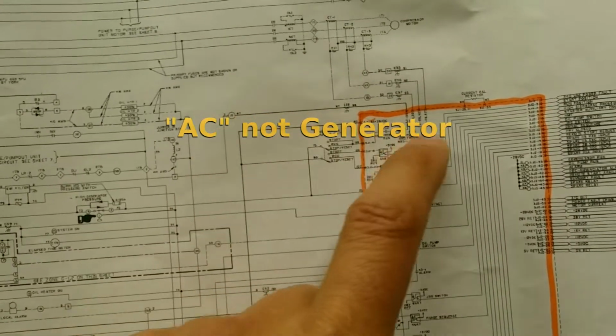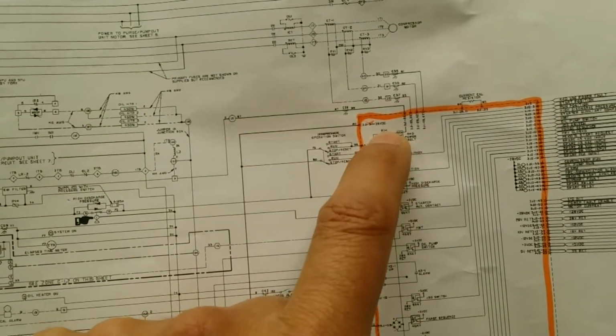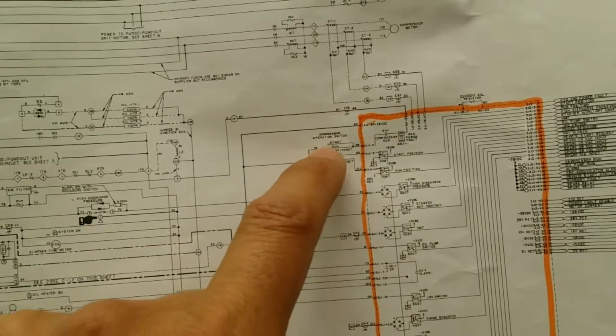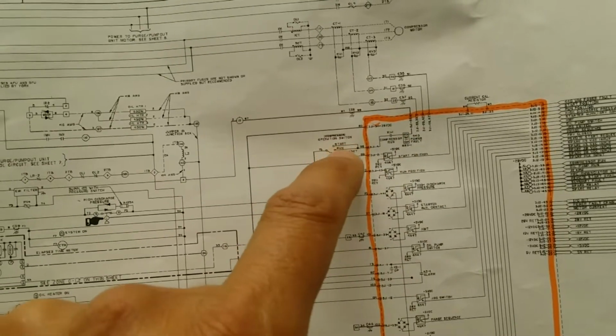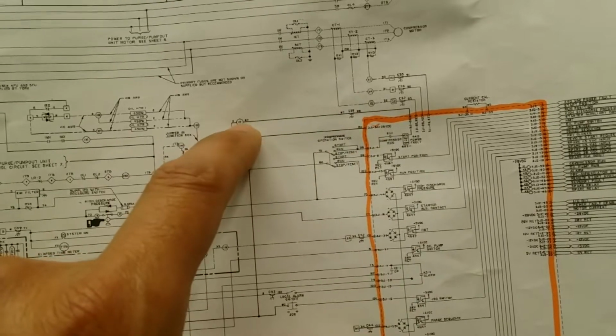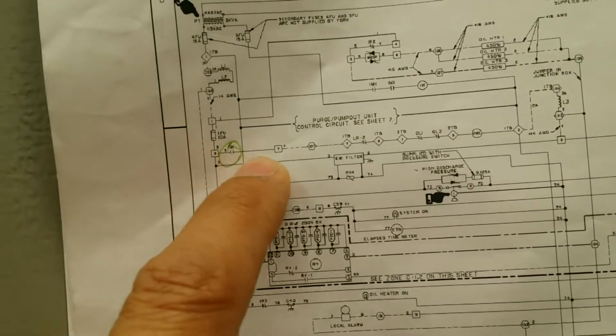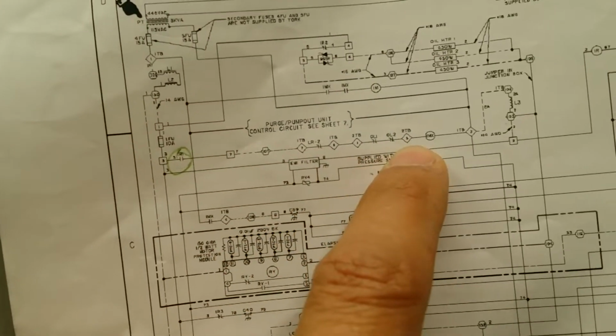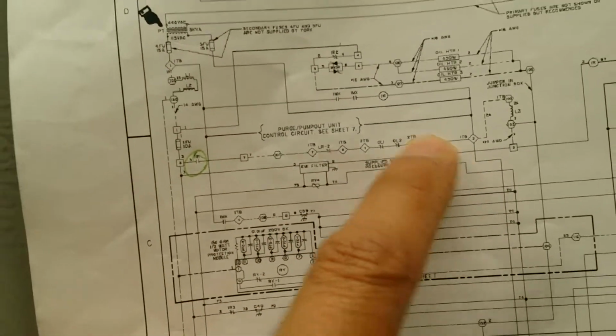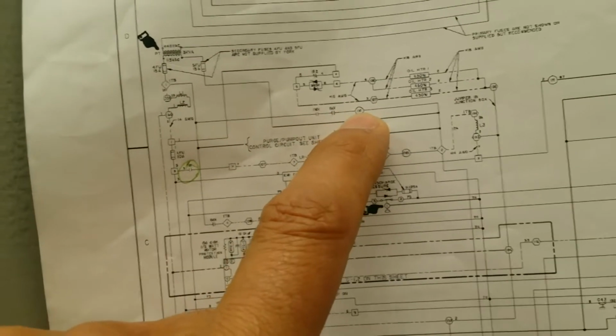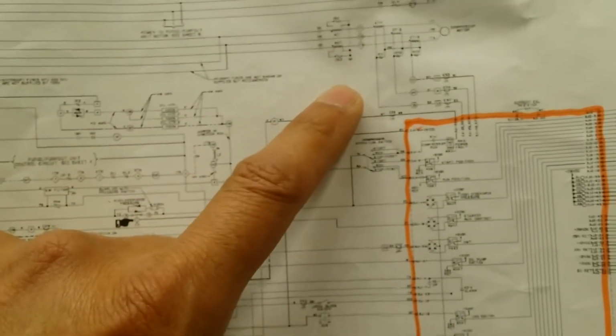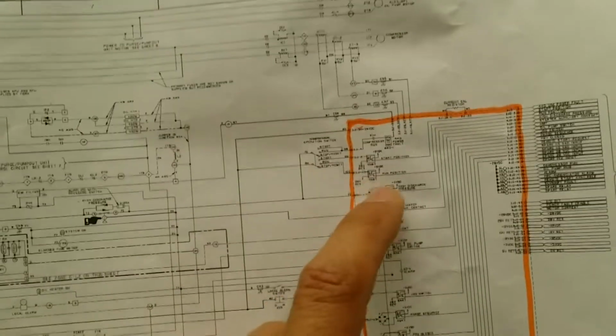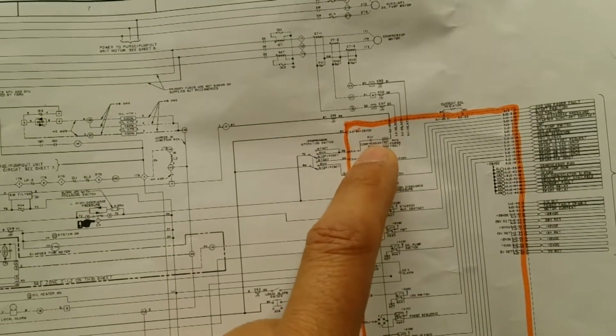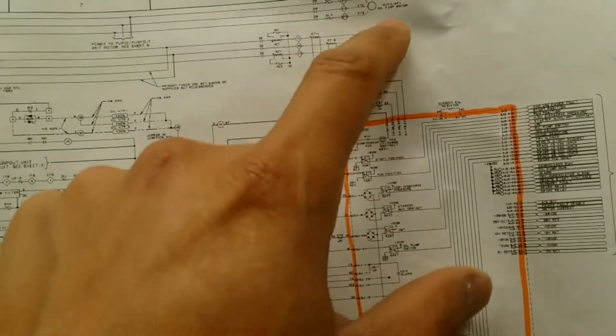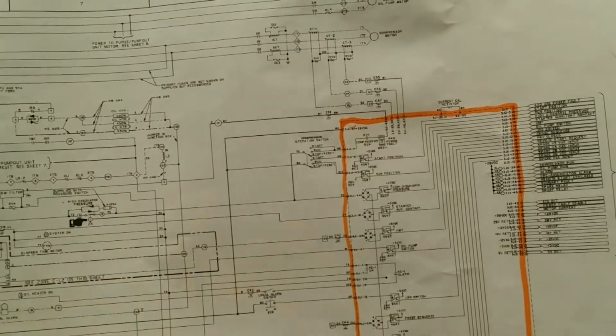Because if you follow the path over here, there is this K1 relay that when it closes, as long as you had this switch in start or run, it will put power in IR, and IR, I'm going to show you over here, when it closes, puts power to this line over here and energizes IMX, and IMX closes contacts, and that's how 1M and the whole thing energizes. So yes, K1 is the one that starts and stops the compressor from the circuit input and output module.